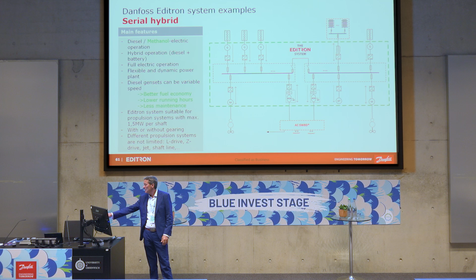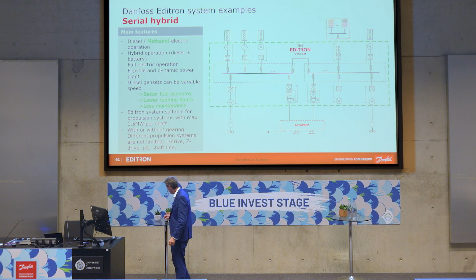On the right-hand side, we've got the battery bank. The battery bank has another clever bit of electronics that goes from the DC - but you can't just connect the DC directly. This bus is running at about 750 volts, so we can't just connect that to a battery; we need to control the voltage to that battery. It's a charge system, handled by another one of those little aluminium boxes that deals with that sector of it.